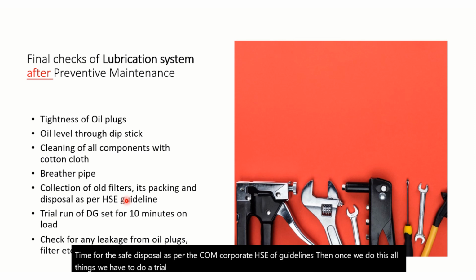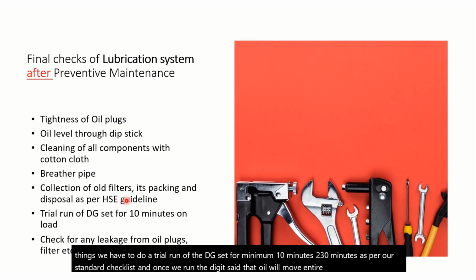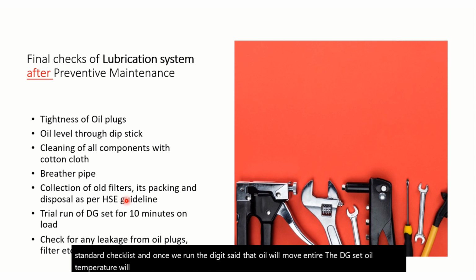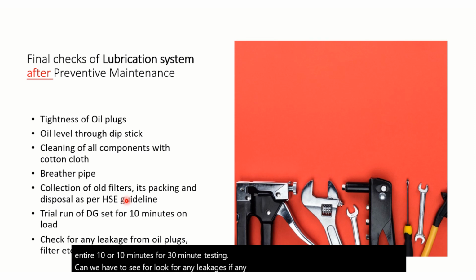for a minimum of 10 minutes to 30 minutes as per our standard checklist. And once we run the DG set, the oil will move through the entire DG set, oil temperature will increase, oil pressure will also increase. So we have to be there during this entire 10 or 30 minute testing, and we have to look for any leakages, if any, from oil plugs and other seals, etc.